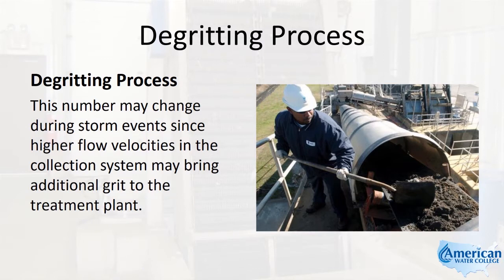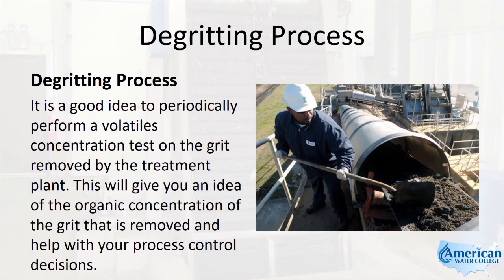This number may change during storm events, since higher flow velocities in the collection system may bring additional grit to the treatment plant. It's a good idea to periodically perform a volatiles concentration test on the grit removed by the treatment plant. This will give you an idea of the organic concentration of the grit that's removed and help with your process control decisions.